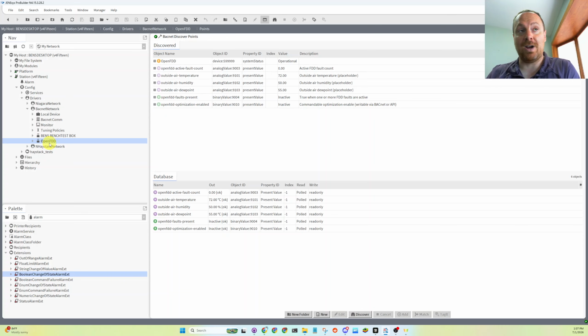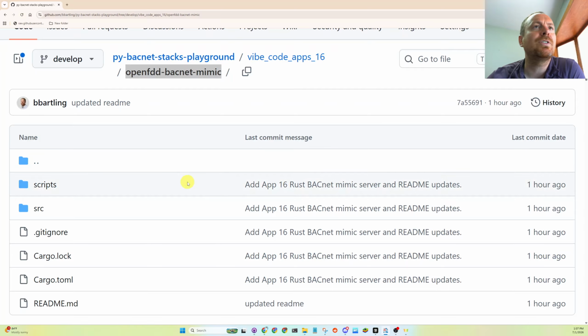So that's how we throttle the BACnet operation technology system manually, by minimally setting up polling on the bare minimum amount of points. And we'll get into all of that later. So I think I have enough to show you here. I'm actually going to minimize Workbench.